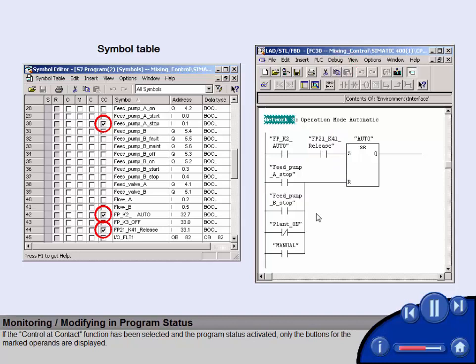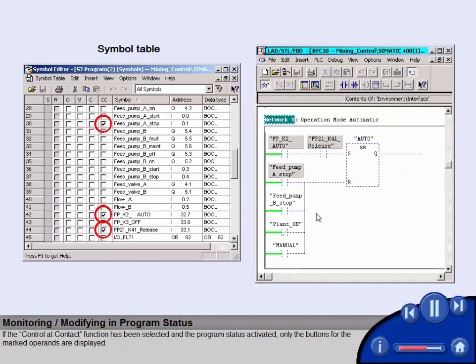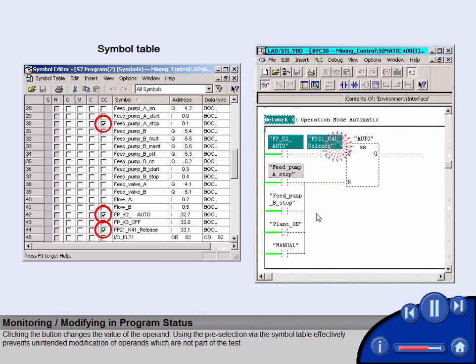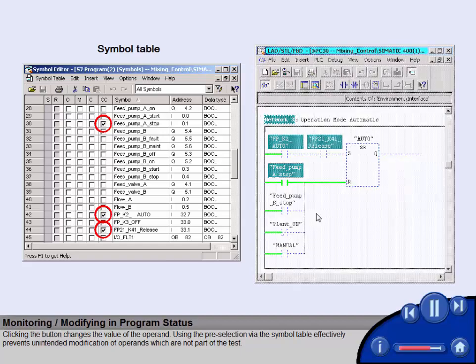If the Control at Contact function has been selected and the program status activated, only the buttons for the marked operands are displayed. Clicking the button changes the value of the operand. Using the pre-selection via the symbol table effectively prevents unintended modification of operands, which are not part of the test.